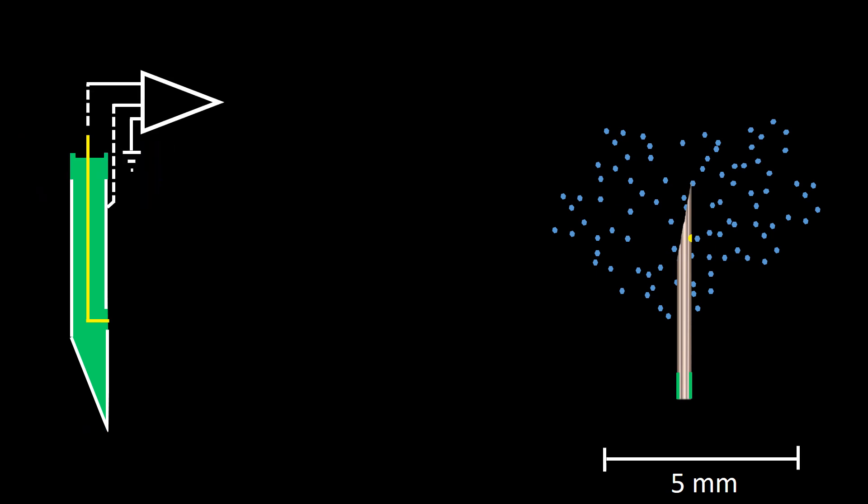The very thin electrode is connected to the G1 position and the distal part of the cannula is connected to the G2 position of the amplifier.